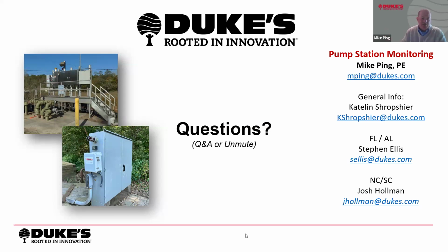There are some fundamental limitations, and just to state it clearly: in fact, in this picture here in the top left, at this particular station, it's in a coastal area, and there was a hurricane, and the entire station was underwater. So the pumps are spinning, and the calculations kind of get goofy when that's happening. But under those extreme circumstances it kind of didn't matter, we were working with them, and all the information that was needed was had. So hopefully that spells it out. It's a calculated value, and it's pretty good. We've done some testing on that against mag meters and so forth.